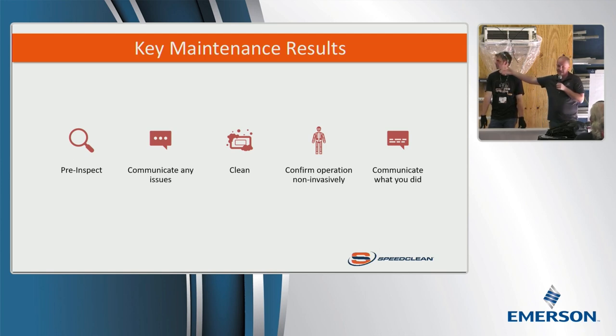Now, how do you pre-assess? I don't want you spending a lot of time on this pre-assessment. I'm literally going to go to beer can cold. Walk outside, check condenser discharge, grab that suction line, just like we've always been taught. If it's running, I'm not going to go through and do a whole assessment, especially since I haven't cleaned it yet, right? Of course, it's not going to perform like it should until it's been cleaned.